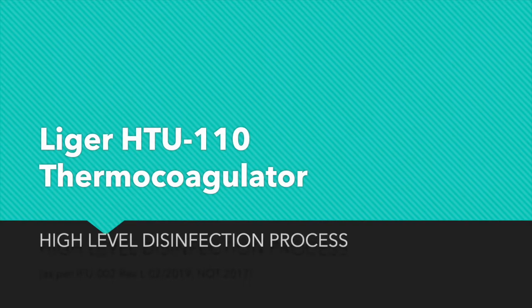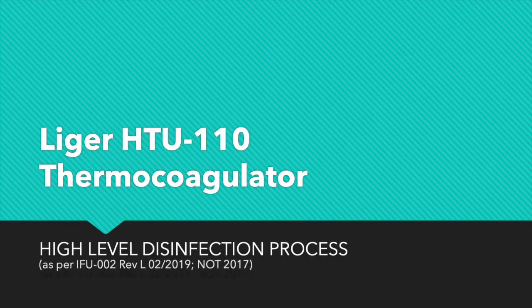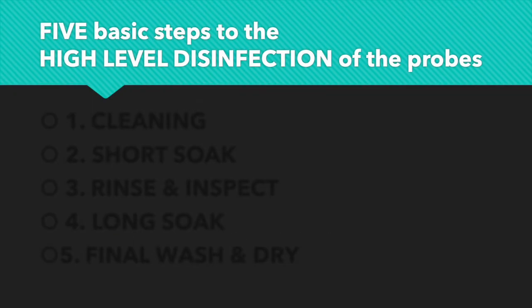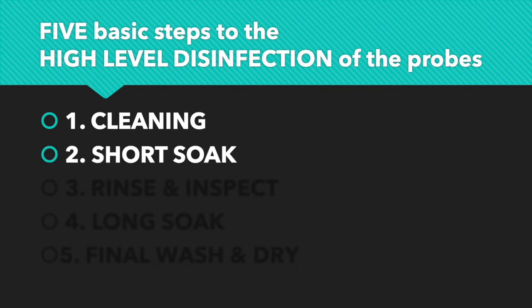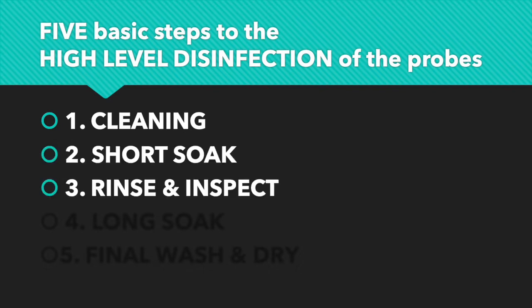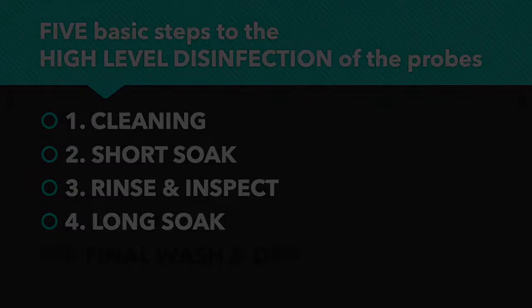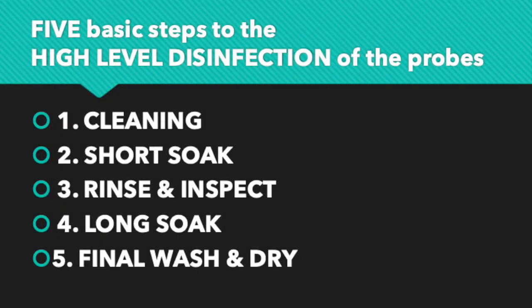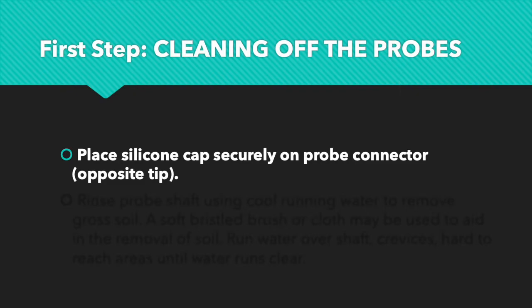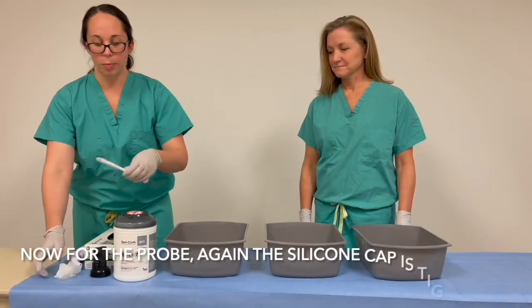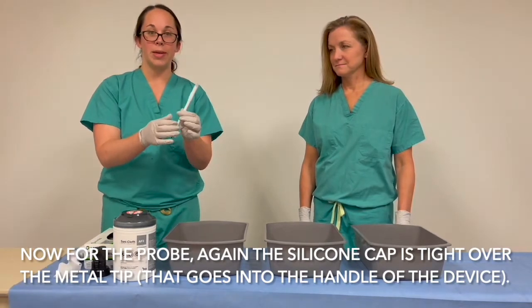For the Liger Thermocoagulator high-level disinfection process, there are 5 basic steps: cleaning, short soak, rinse and inspect, long soak, and final wash and dry. The first step is cleaning off the probes. Now for the probe. Again, the silicone cap is tight over the metal tip.